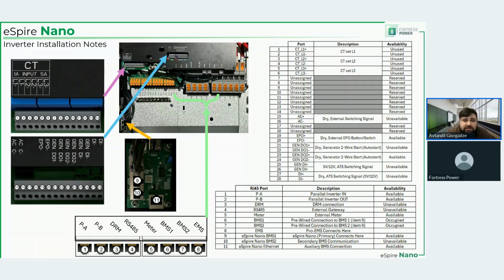This is the switching signal for the ATS that may be upstream of the inverter. But remember, we're not allowing the ATS to be upstream of the inverter. So these ports are not going to be used because that use case does not exist with our system. And we can repurpose this in the future, maybe.